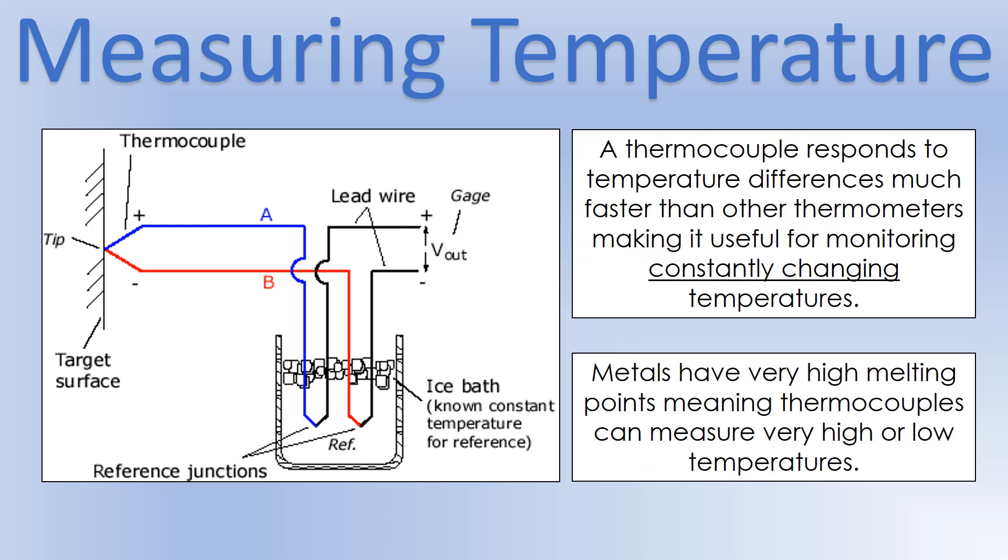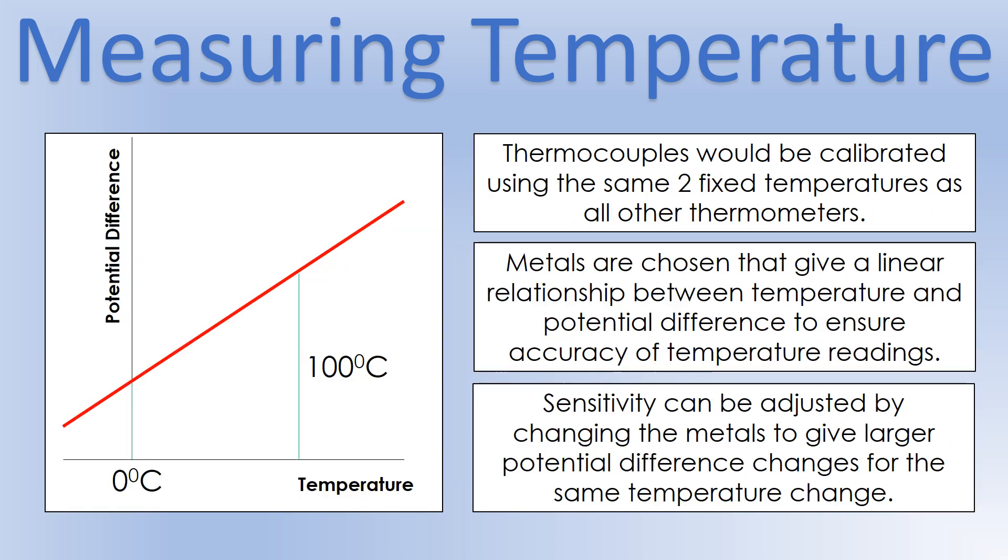So the benefit of a thermocouple is the speed at which it responds. So electron diffusion happens very quickly, even though there are different rates. So it's very effective for measuring something where the temperature is changing continuously. You can take measurements very quickly. And the other thing is, because this is made out of metal, metals have very high melting points. So it gives you a very large range of temperatures that you can take measurements over, unlike your liquid based ones that we've seen earlier.